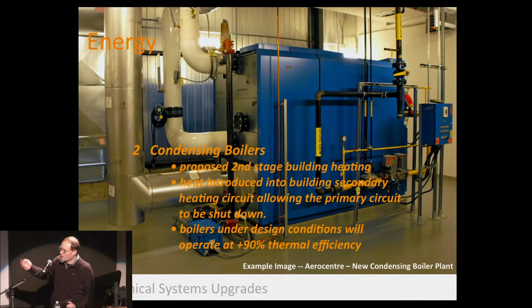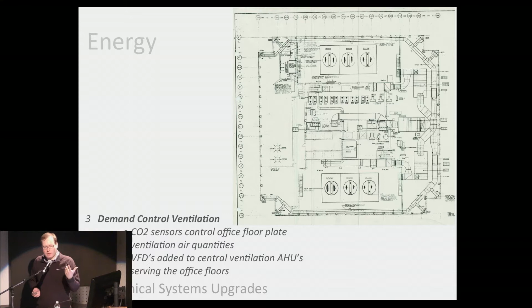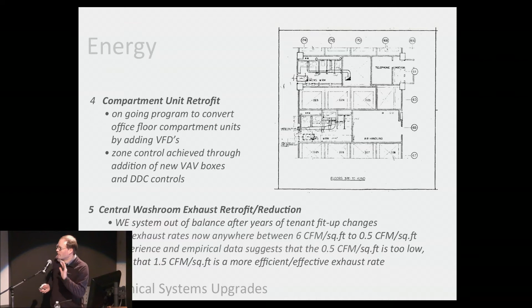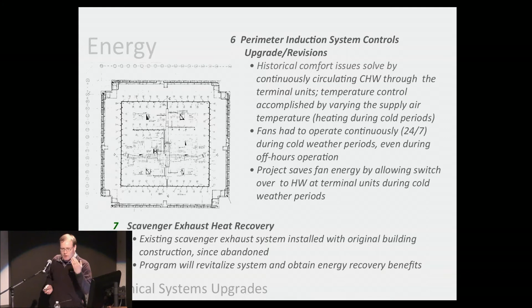We put in all condensing boilers, 90 plus efficiency. All the ventilation was demand control. We put CO2 sensors on all the return air decks so that we only ramp up the ventilation as we occupy the building. We looked at everything, including washroom exhaust. We put a scavenger heat recovery on the washroom exhaust. The perimeter induction system that I talked about requires that primary heat, and we turned all the motors to direct drive motors so that they could be ramped up and down, not just on and off. Everything had control. We put variable speed drives on all the drives.